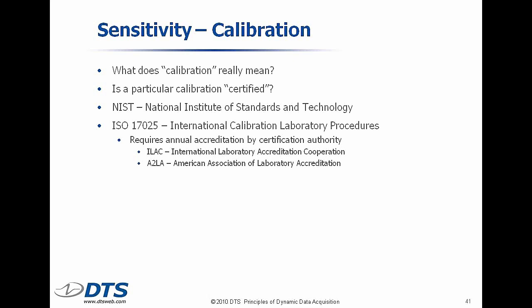These days, you might hear the term ISO 17025. ISO is International Standards Organization. 17025 is basically the internationally recognized practice for making measurements for calibration. And so DTS in the last year became certified by the A2LA, which is the American Association of Laboratory Accreditation. Basically, we're accredited that we know how to measure stuff in accordance with the ISO standard. And you're going to hear more about that in the coming years. 10 years ago, nobody really cared much about it. But when you do your calibrations, you're going to start hearing people say, is it ISO accredited?